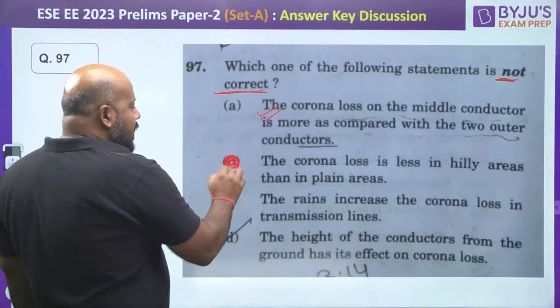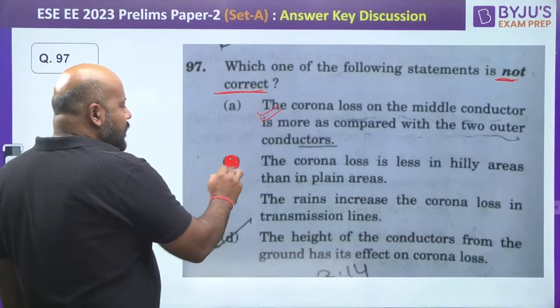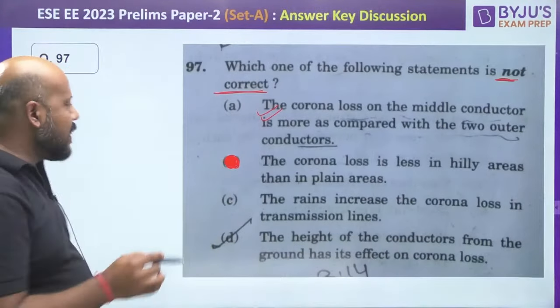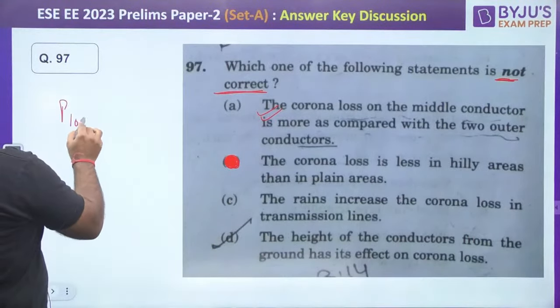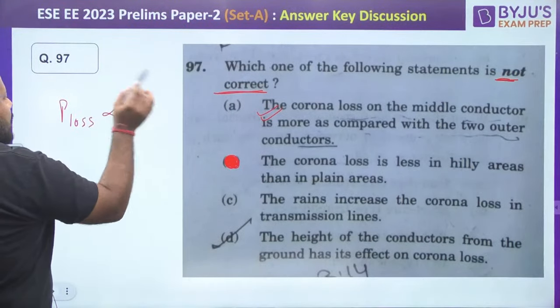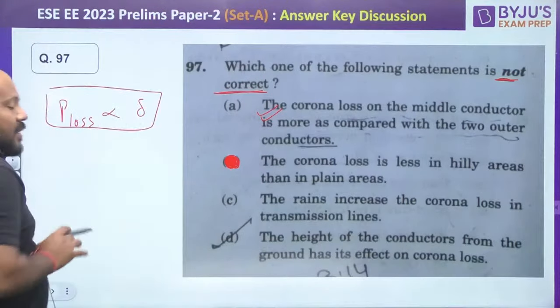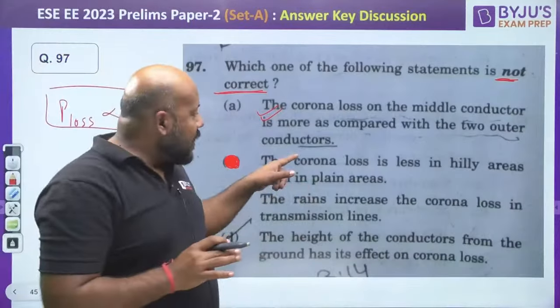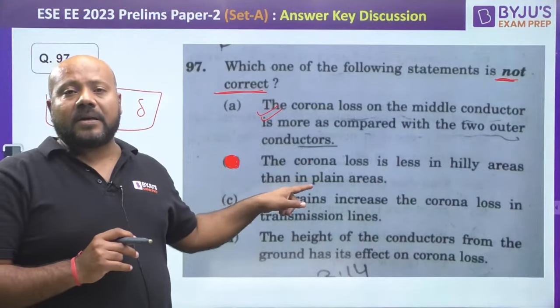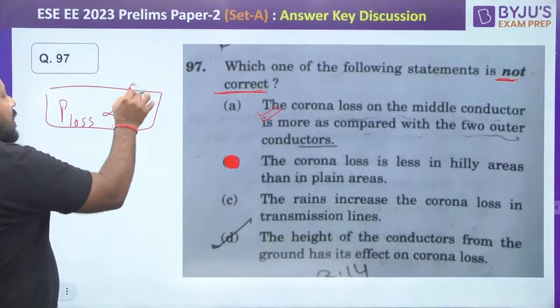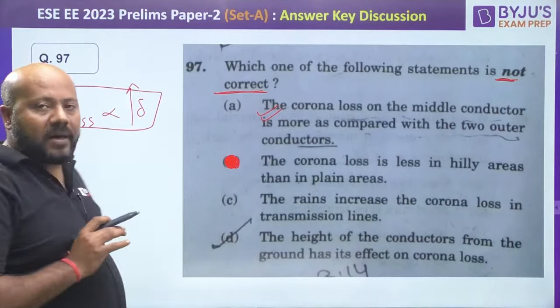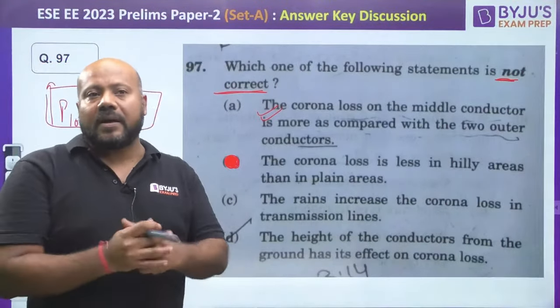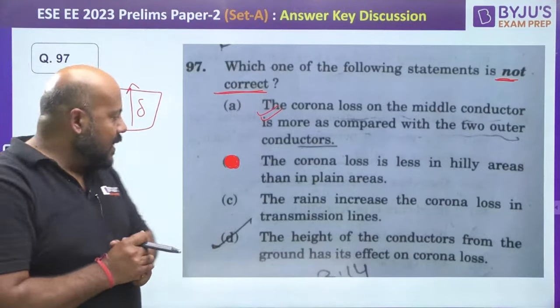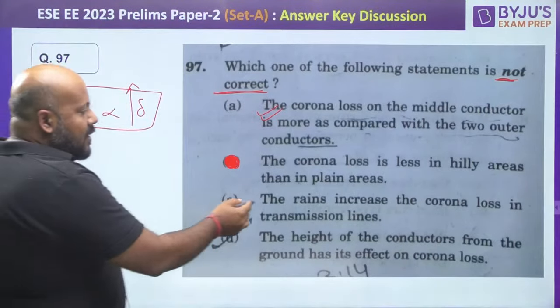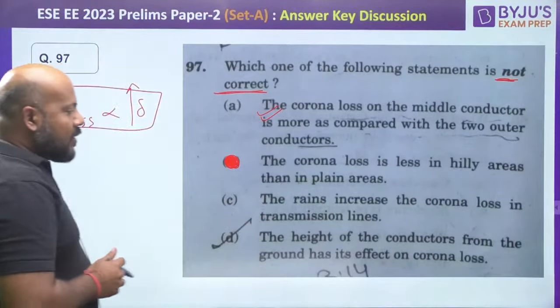What logic do you apply here? Corona loss is directly proportional to the air density. In hilly areas, the air density is higher, so corona loss is higher compared to plain areas, where air density is less. Option C says rain increases the corona loss in the transmission line, and this is correct.